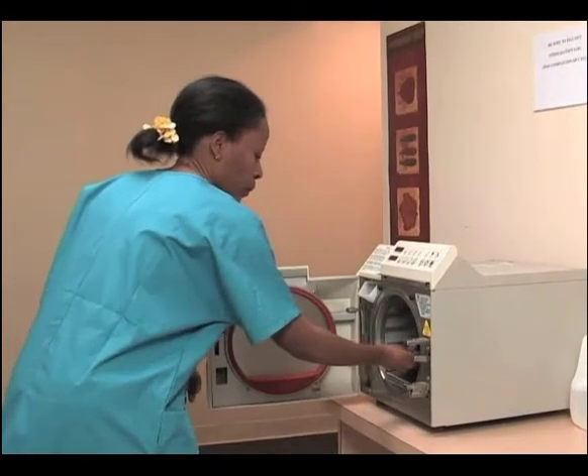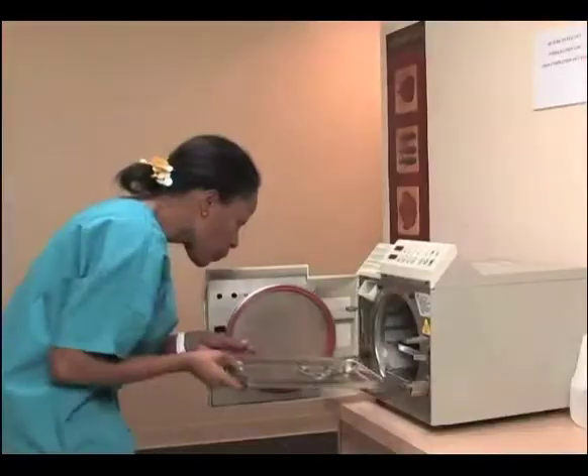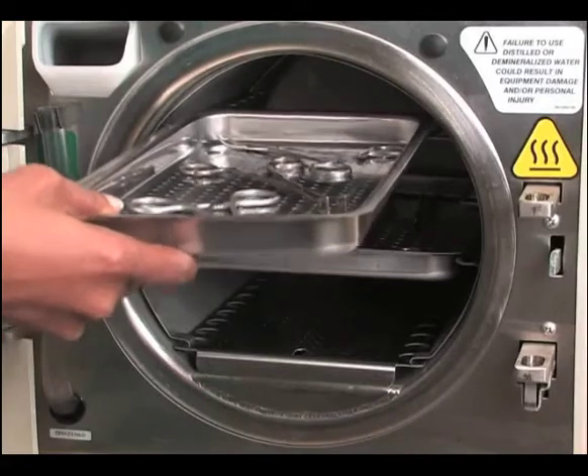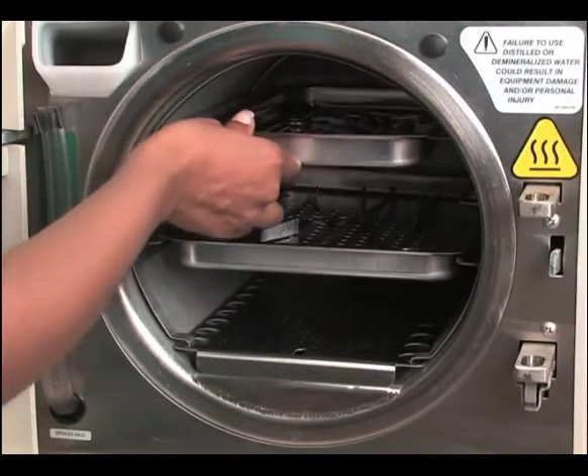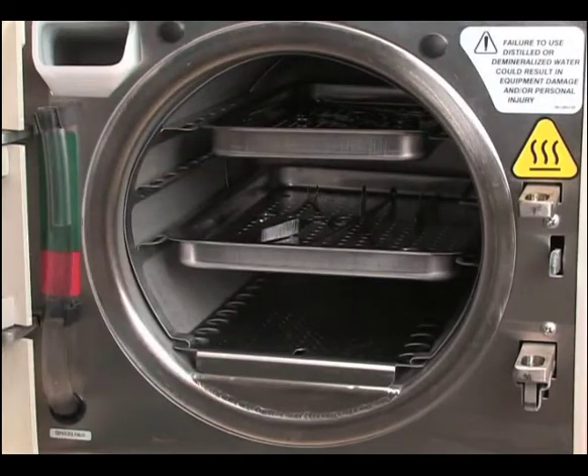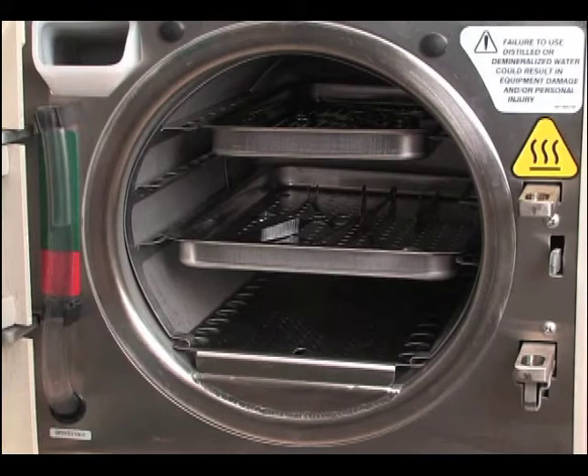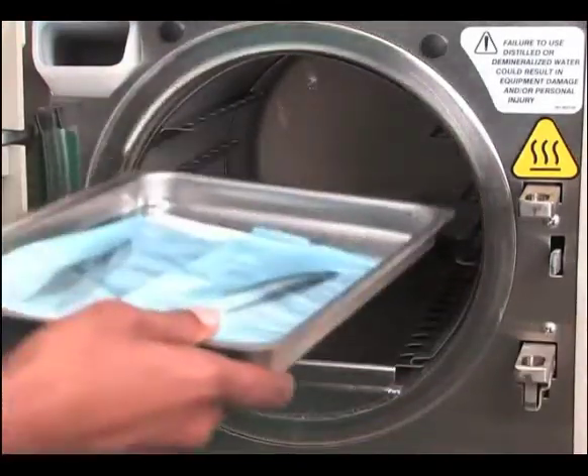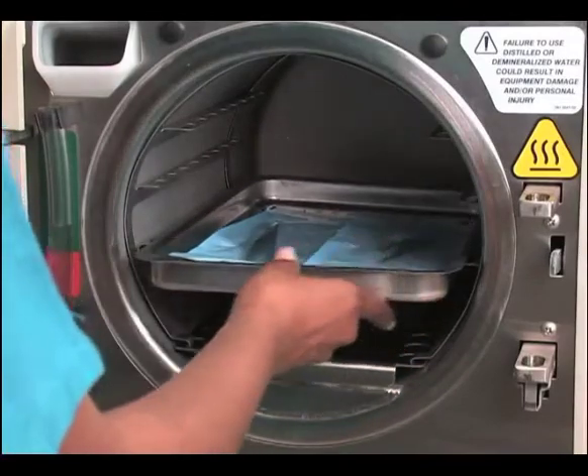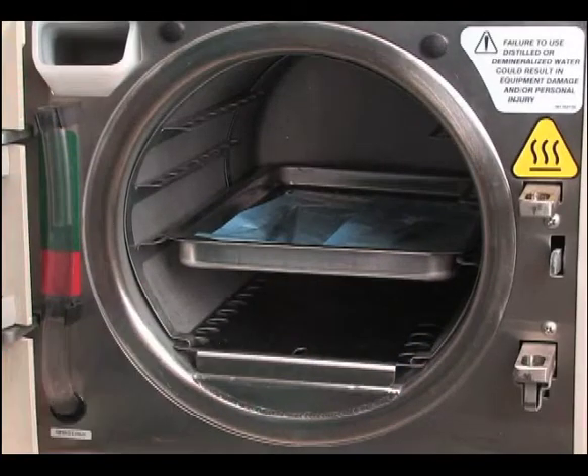The autoclave must be loaded correctly to ensure steam penetration and complete sterilization. Steam must reach all surfaces for the required time and at the required temperature to kill all microorganisms. Loading guidelines include the following. Position autoclave trays 1 inch apart. Sterilization pouches can be placed on their sides or flat depending on the model of the autoclave.